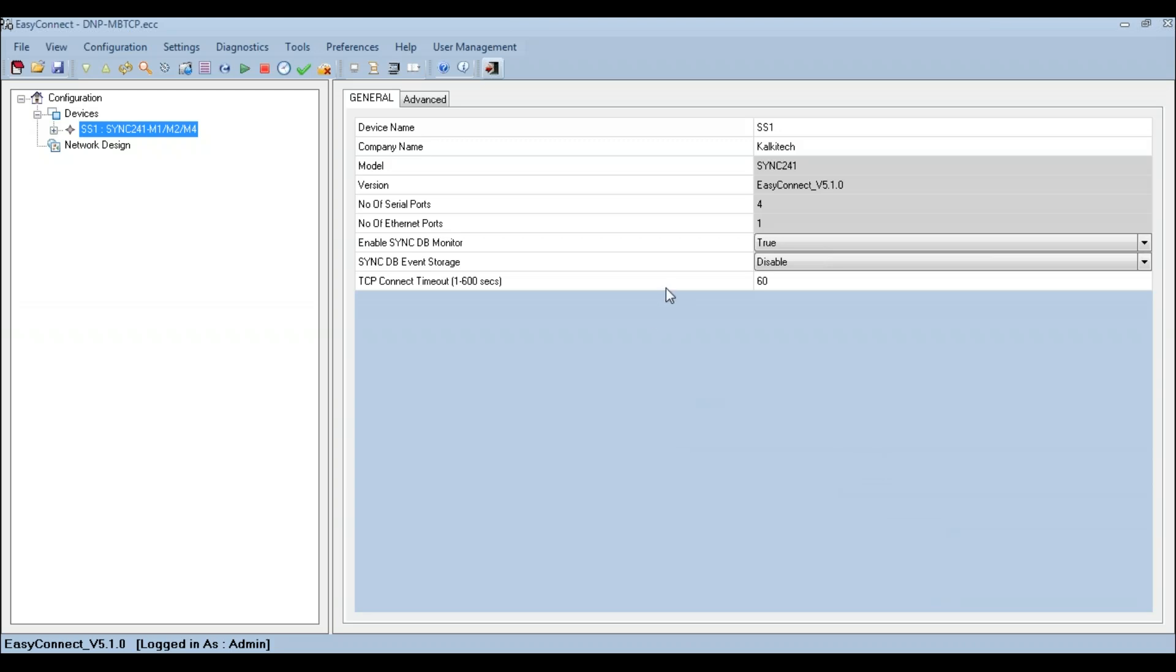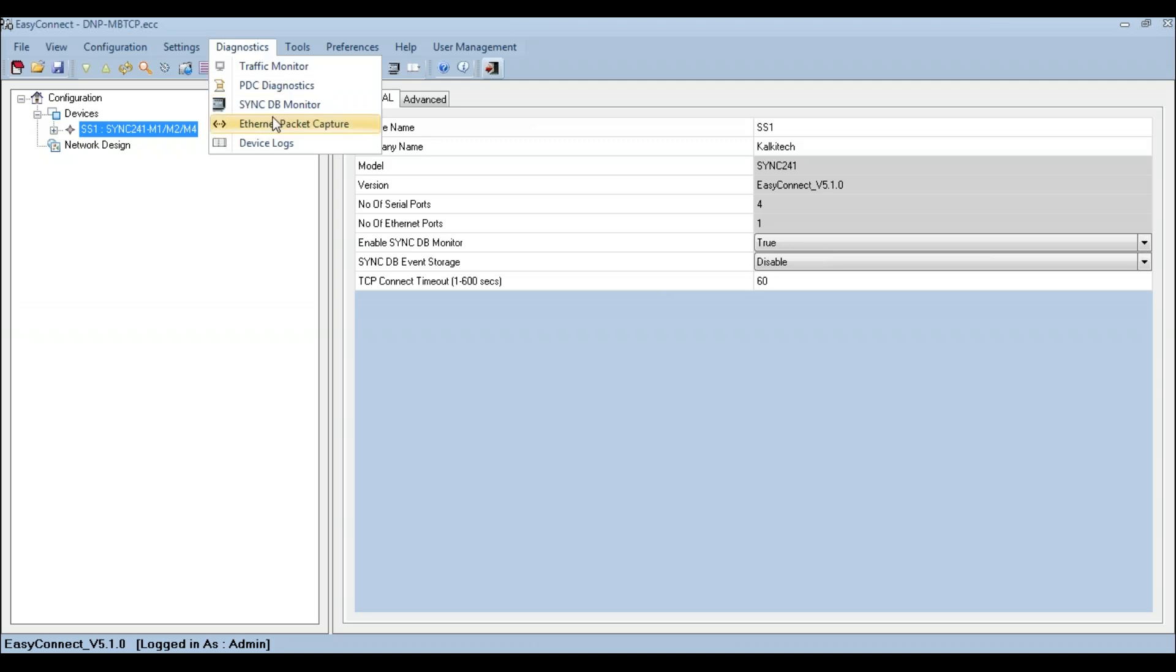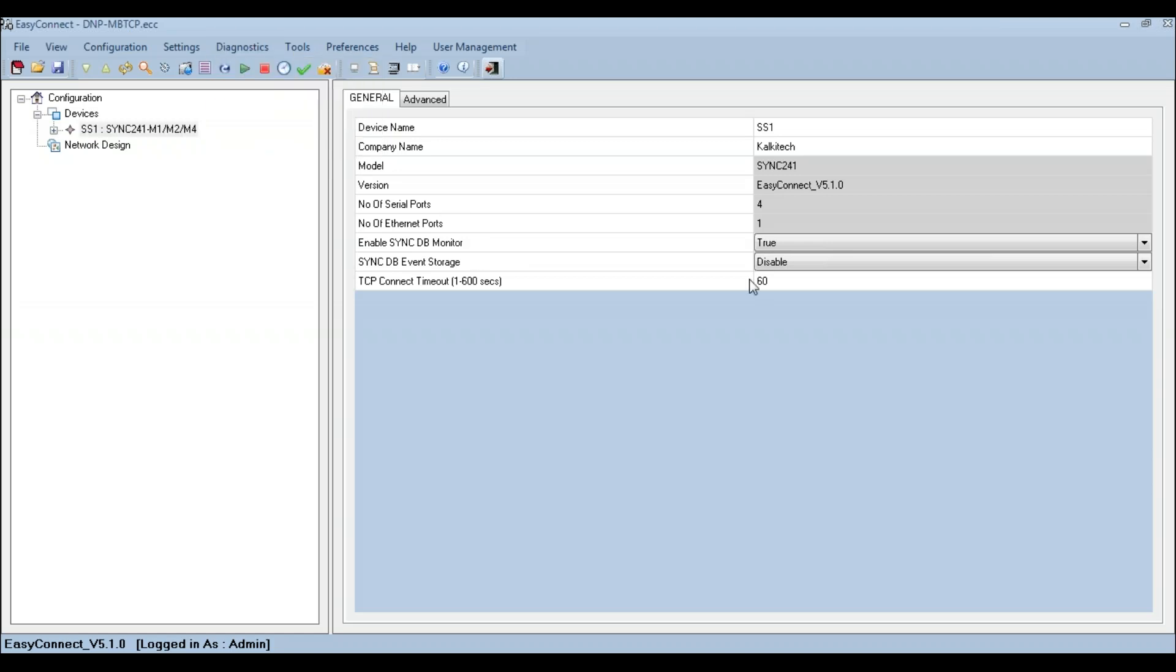EasyConnect provides two diagnostics options to monitor the communication between SYNC device and IED. The Diagnostic Traffic Monitor and Diagnostic SyncDB Monitor can be used to monitor the real-time communication configuration between the SYNC device and the IED. Ensure that the Enable SyncDB Monitor is configured as true before downloading the configuration to activate the SyncDB functionality.